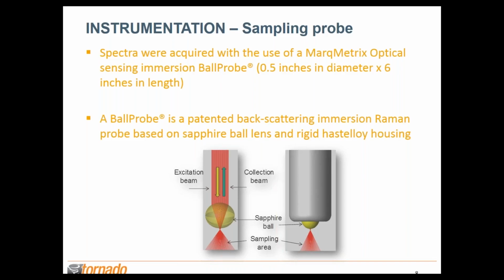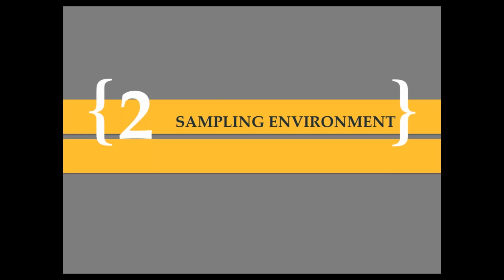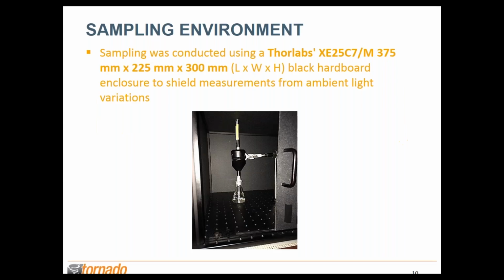Next, addressing the sampling environment. With optical measurements, Raman and infrared, often you have to take a background measurement. In Raman, we call it a dark, and that's to compensate for potential ambient light variations. If we can't shield from those lighting variations, one can take a dark scan, which would map the given lighting conditions. But if they were to vary with time during the course of the acquisition, then the dark scan may not be representative, and that would force you, for ongoing measurements, to take a dark scan more frequently.